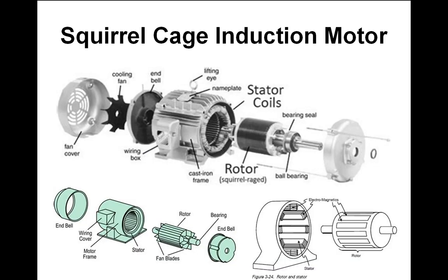Next — squirrel cage induction motor. You've got a ring on each side connected by wires. When the three-phase electromagnetic field orbits around, a current is induced into the squirrel cage, which pushes current through the connecting lines and generates a magnetic field. You then have two magnetic fields that spin the rotor around. The huge advantage is the rotor has absolutely no electrical connection whatsoever.